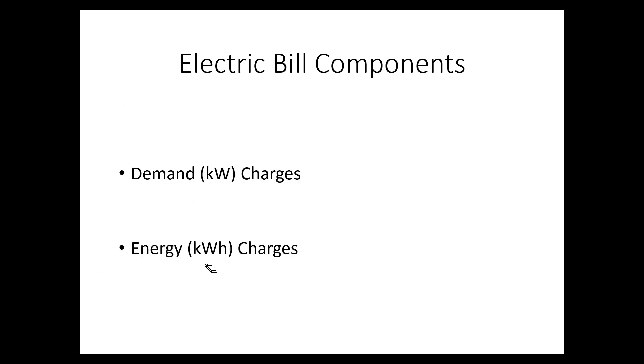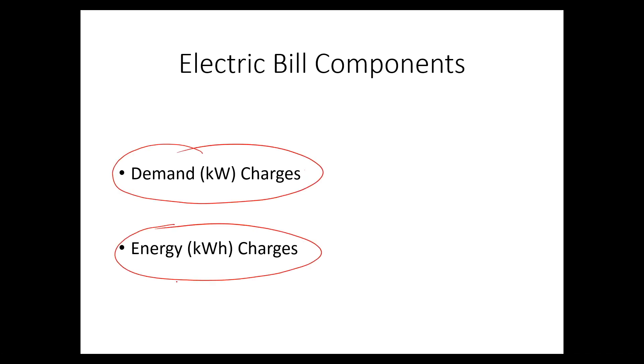The next two items you'll find on most electric bills are demand charges and energy charges. Energy is pretty obvious — it is the total number of kilowatt-hours you use over a month's period of time. Demand is more like a flow rate — how much energy you're using per second. They measure this every second and average it over 15 minutes. Whatever your maximum average flow rate during a 15-minute period, the utility remembers that.